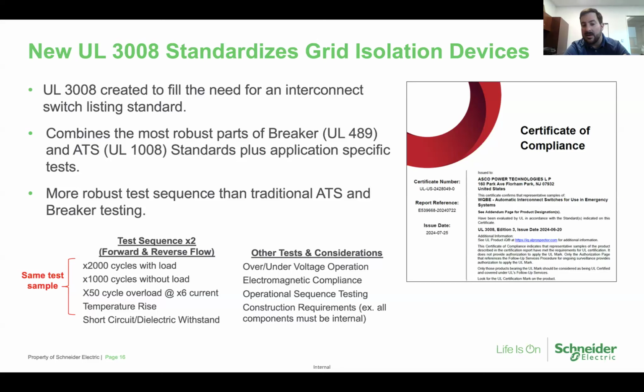Can a breaker provide isolation? Well, yes, it can, but not to the same levels as a UL 3008 qualified isolation device, which has the right controls, sequences, and performance for the interconnect application. And why would you expect any less when that's what you've always expected out of UL 1008 for your transfer switches, right?